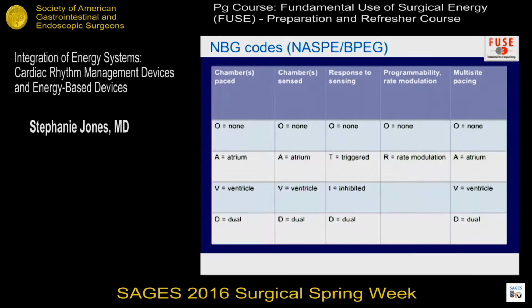The fourth column is rate modulation, which is more common in newer devices. It allows for a separate rate if somebody, let's say, is exercising. It'll pick the rate up. It'll often be detected by bioimpedance, so if their respiratory rate increases, it'll increase their heart rate. That's something that we often want to turn off for the OR because you might not want an 85-year-old patient with a heart rate that's elevated through the entire procedure, which can sometimes happen through not so much the surgical energy, but often the anesthesia ventilator can trigger this.